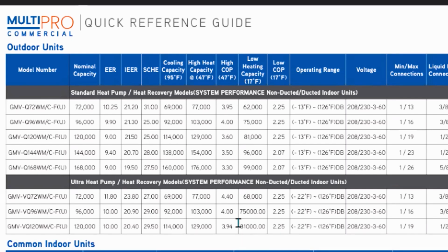So on these, again, as we mentioned, to change it from a standard heat pump or the Ultra heat pump to heat recovery, there is a simple dip switch that we will show you a little later in the manual where you would actually change that. So I guess let's elaborate on that just a little bit. Heat recovery is going to be a 3-pipe system. Correct. Going into a mode box. From the mode box, you're going to go to your indoor units.